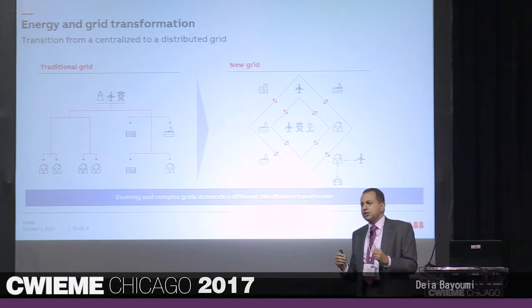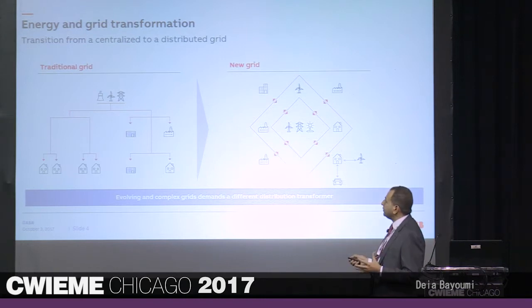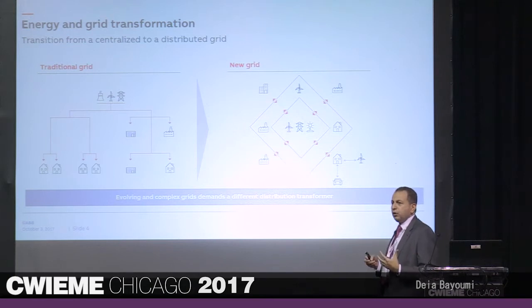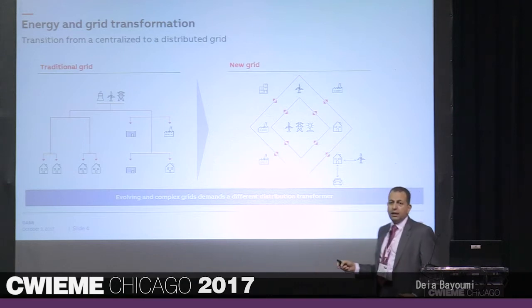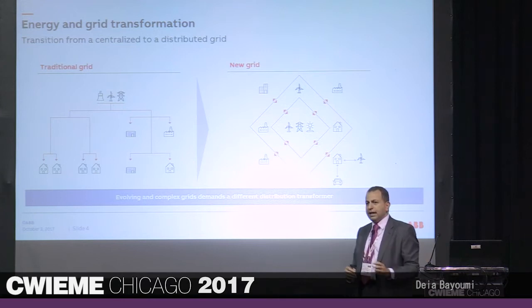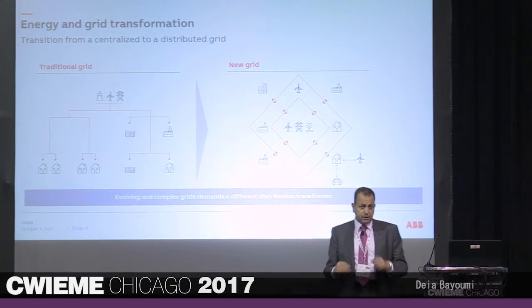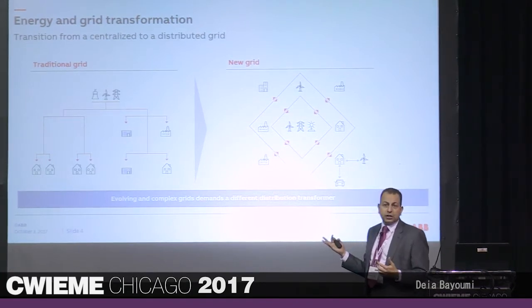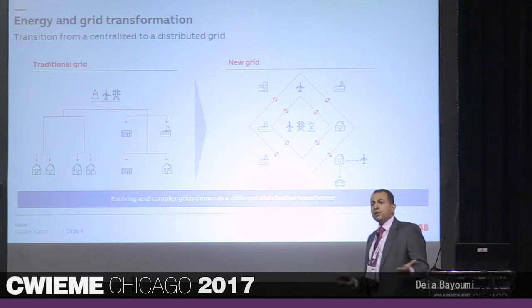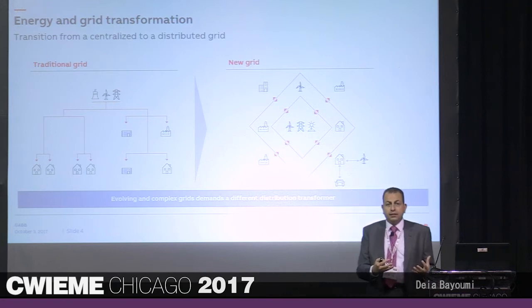The unique challenge here is that we developed as an industry on the power side in terms of monitoring and control, while the transmission and sub-transmission grid is much more stable. Building a substation takes about two years; an HVDC terminal takes five to ten years — there's much more planning. Versus at the distribution level: adding a neighborhood, an IKEA store, an airport terminal — how much planning is happening? Mostly pulling cable and getting permits. So there is much more stress on the distribution grid, yet all monitoring devices so far focus on the power side.